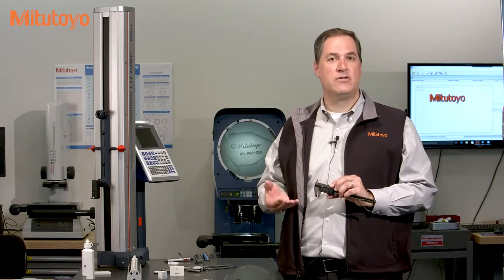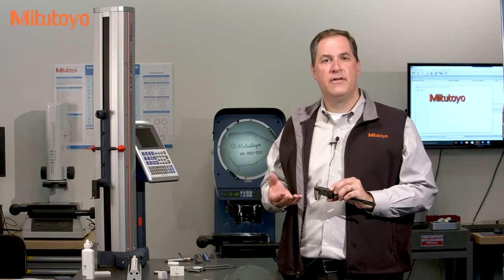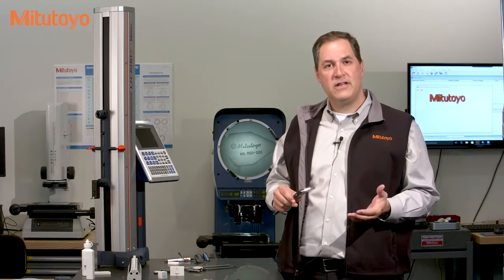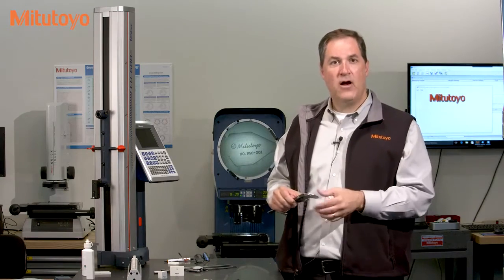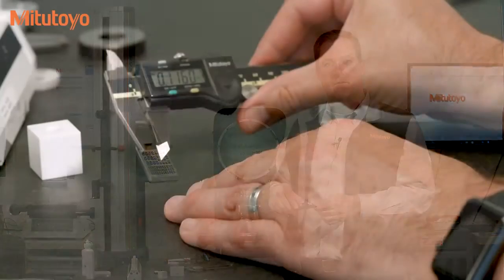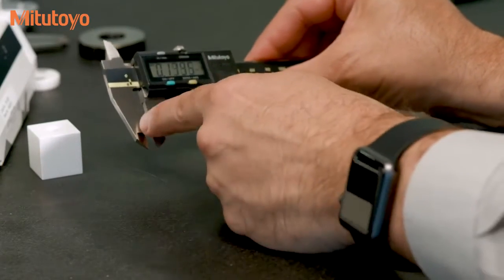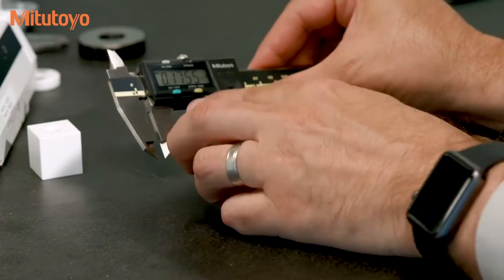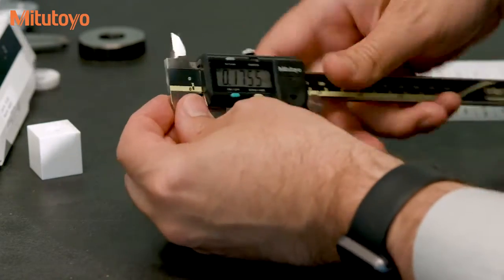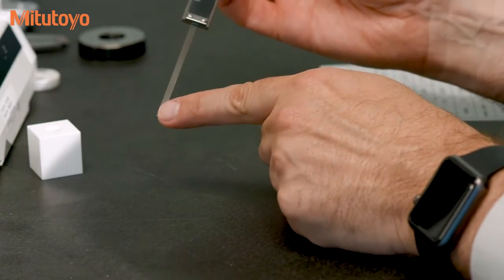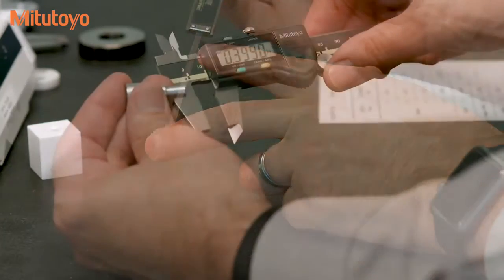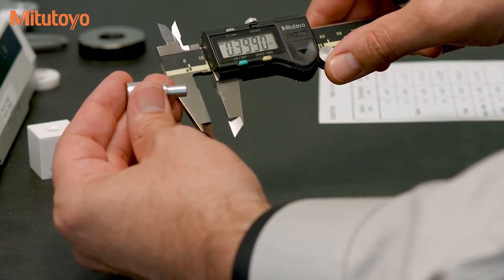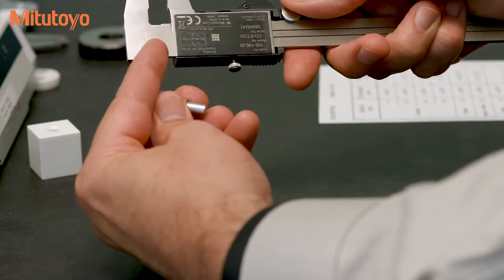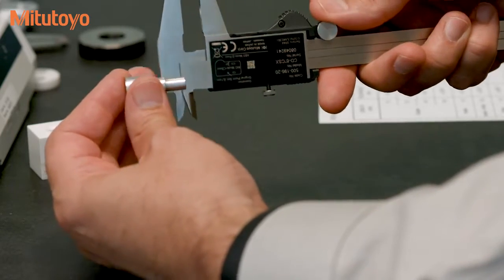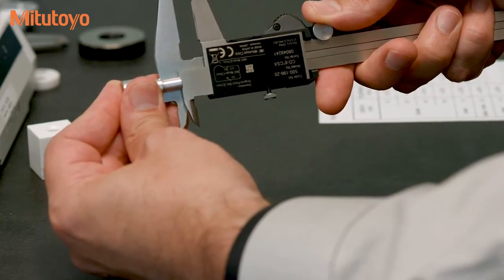The very common caliper, like this one here, has 4 different types of measurements it can make. And therefore our calibration method needs to be properly engineered to sufficiently and most efficiently hunt down the potential errors. As already mentioned, this caliper can make both outside and inside measurements. Most calipers like this, up to 12 inches, also have some type of depth bar for making measurements into holes or slots. The 4th type of measurement that's possible with this caliper is the step measurement, which uses these 2 faces to make measurements like this step height on this cylindrical workpiece.